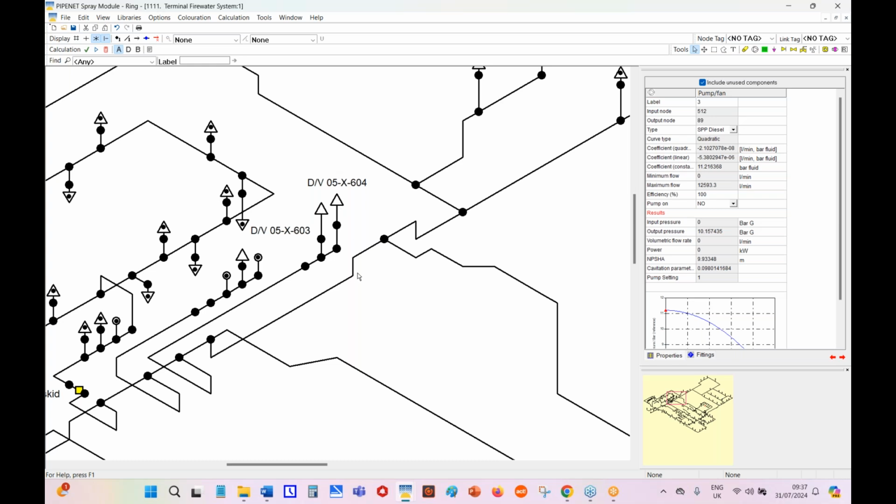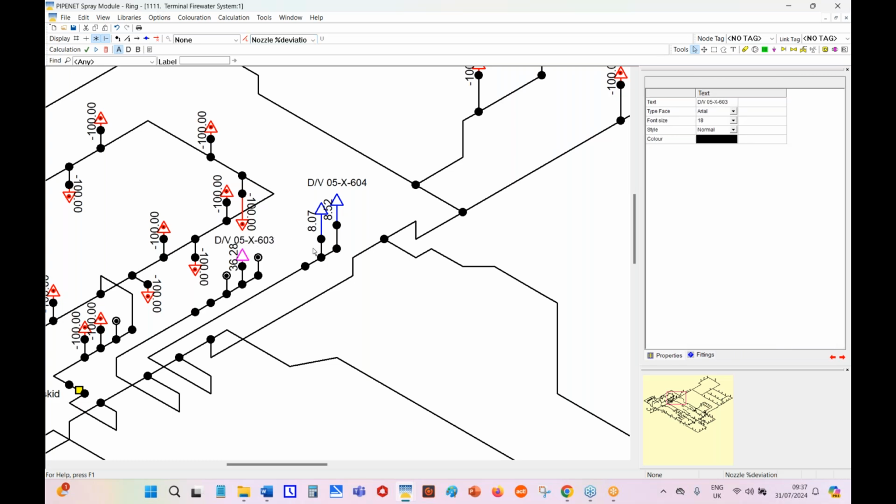And the only thing is, hey, if we switch off 2 pumps, will the users still get what they're supposed to get? Yeah. See, it's fantastic. Look at it. You're getting 8%, 8.5%, 36.3% more than what is required. So your client is very happy, and your manager is very happy. He says, good boy.